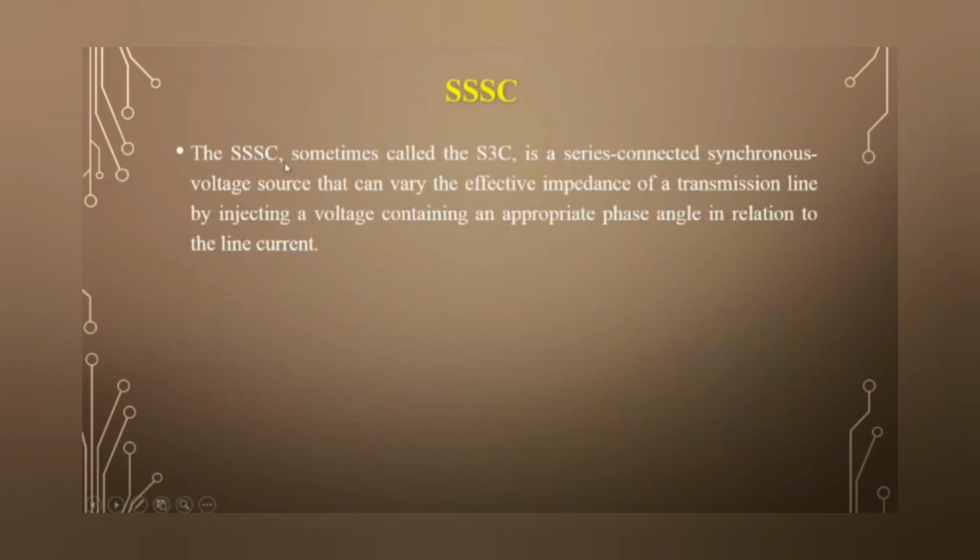So the SSSC, sometimes also called the S3C, is a series connected synchronous voltage source that can vary the effective impedance of a transmission line by injecting a voltage containing an appropriate phase angle in relation to the line current. So by injecting the voltage, you can control the line current and the effective impedance of a transmission line.